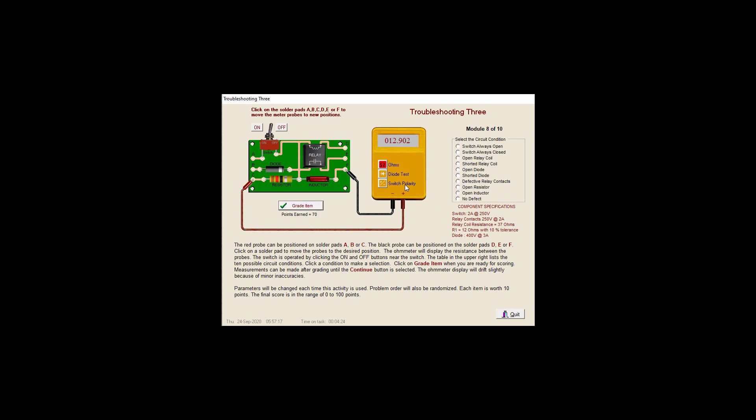Oops. Another bad one. So let's check this one. So we've got 49, which is 12 plus 37. Perfect. And let's check our contact. That's good. It's open. Just for grins. Let's check our switch. I know where it's at. But let's check our switch. Good. We have an open inductor. Let's go ahead and confirm that again.